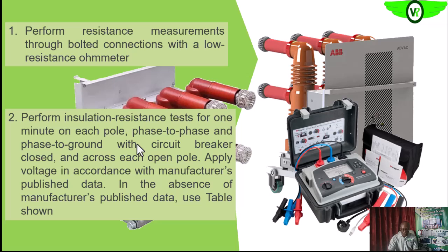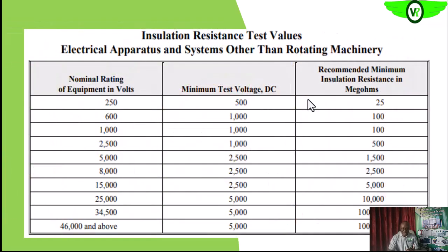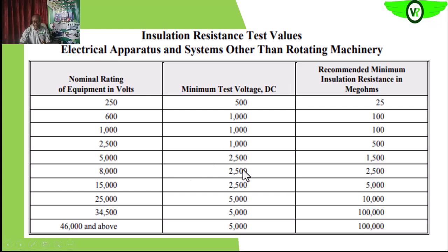We also want to check the insulation resistance of the circuit breakers. That is, we want to look at the insulation between phases and between phase and ground. So we want to follow our laid down procedure in our facility. What is expected or recommended by our facility, or by the equipment manufacturer, is what we look out for. In the absence of that, we can use this table as usual. We have the operating voltage on the far left, in the middle the amount of test voltage that we can inject, and then the minimum resistance level. If you are not too familiar with how to carry out insulation resistance tests, you can check the description below for a link to the video training on how to perform insulation resistance.